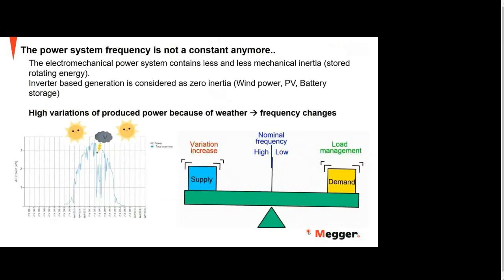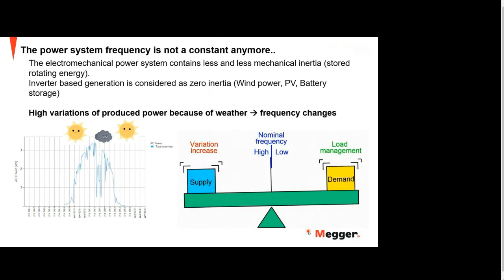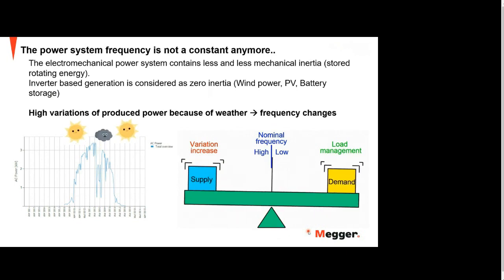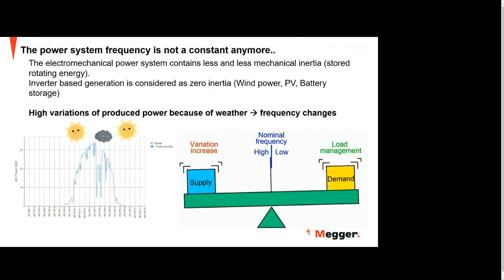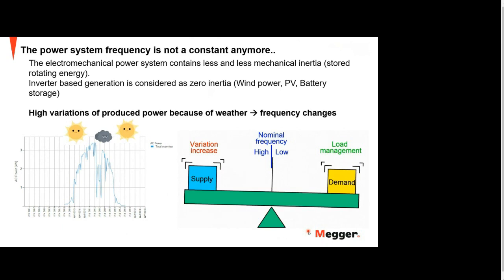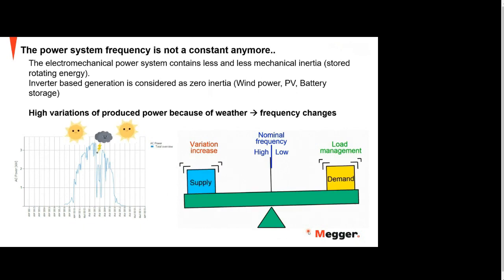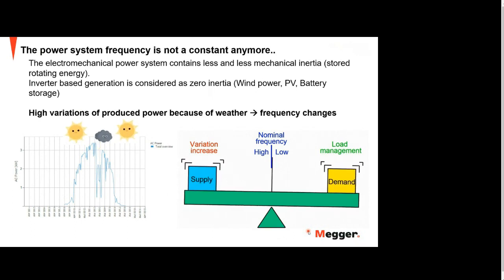So in a power system, the system frequency is not constant anymore. The electromechanical power system contains less and less mechanical inertia, stored rotational energy. Inverter-based generation, which is coming more and more nowadays with the distributed power plants, is considered as zero inertia, like wind power, photovoltaic, battery storage. So with high variations of produced power because of the weather, the frequency could actually change. So you need to have a balance between the supply of the power and the demand, the load management. That's very important nowadays, and that's why we more and more try to have smart grids which are more functional.